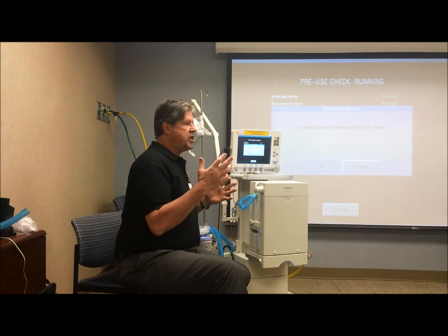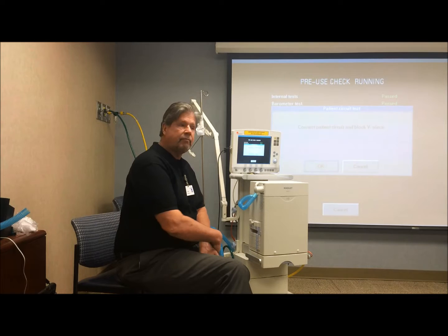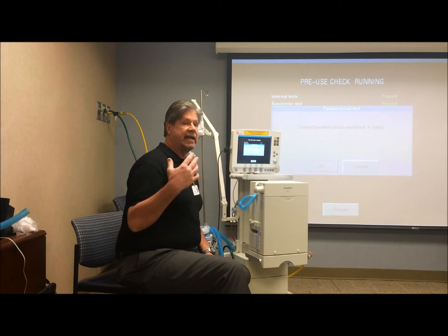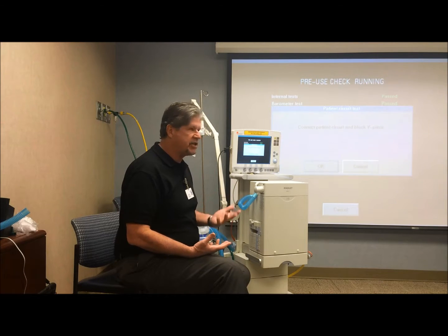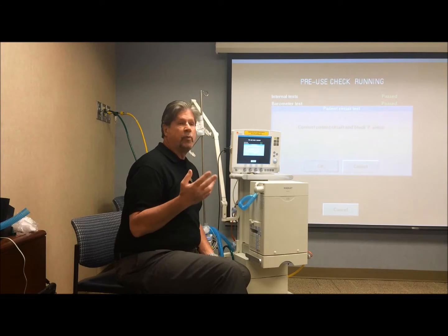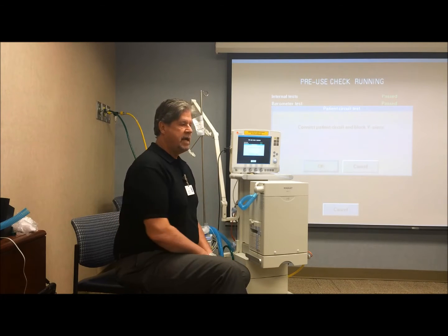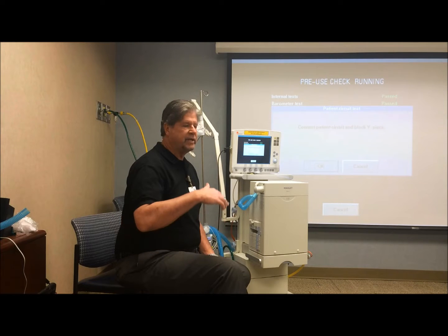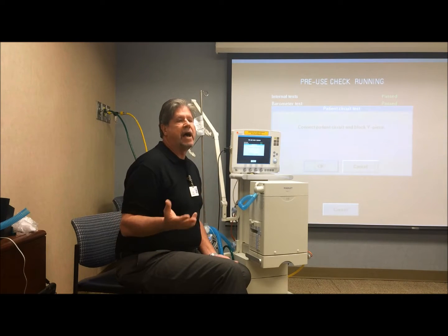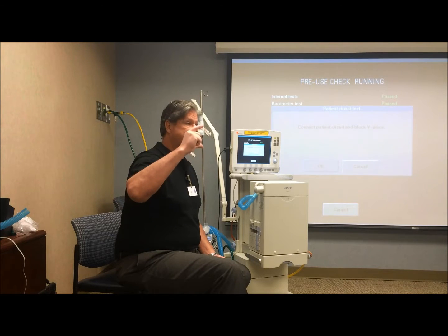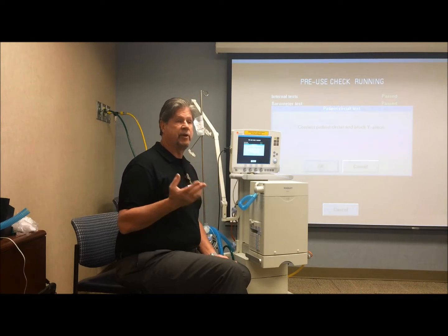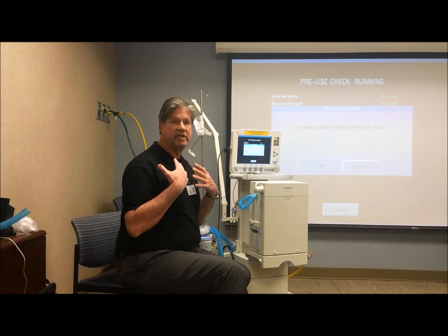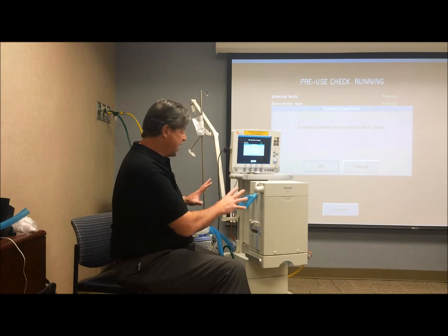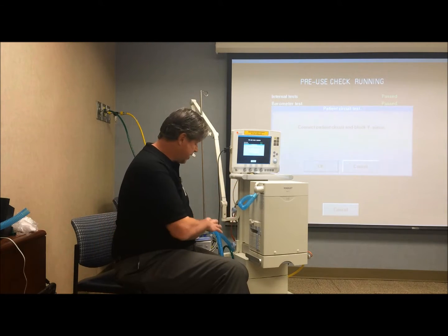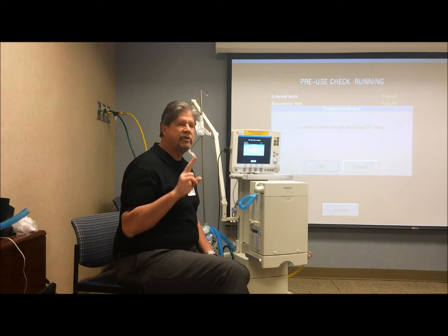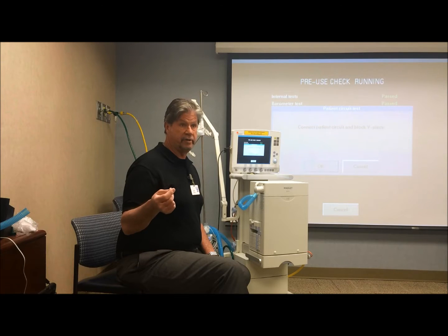And so when you do that particular test, the ventilator knows how much is lost, and it can compensate for the lost volume. So typically on a patient, for example, let's say we're an adult patient, we're delivering a 500 cc tidal volume to him. And when we're ventilating him, his peak inflation pressure is 30 and his PEEP is 5. So his ventilating pressure is 25, right, in that case. It takes 25 centimeters, or creates 25 centimeters water pressure, to deliver that 500 cc volume. Well, generally speaking, a circuit without an HME, without an active humidifier, loses about 2 cc per centimeter of water pressure to the circuit.